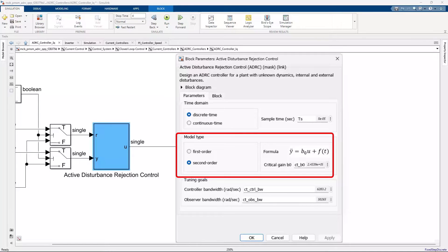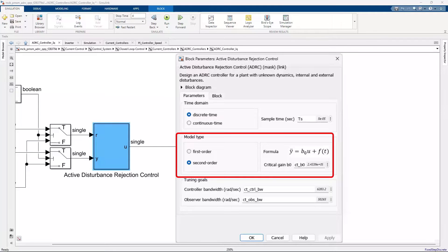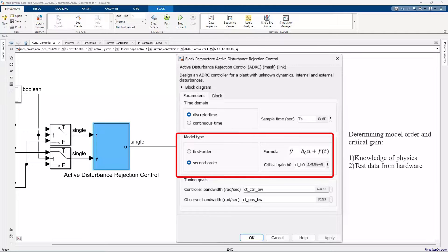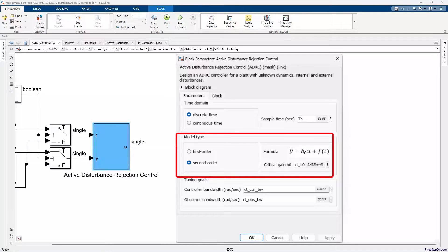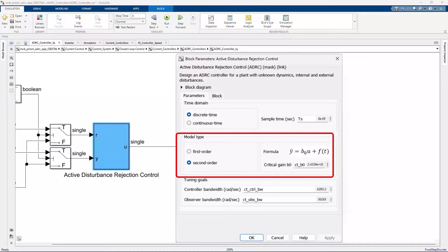A point to note here is that the open loop test is just one way to approximate the plant dynamics. You don't have to do it if you have the information or better way of doing it. In this scenario, the plant cannot be tested for a purely open loop response because of stability concerns. So, we use a PI controller with initial PI gains to operate the plant in a region that is safe and stable.